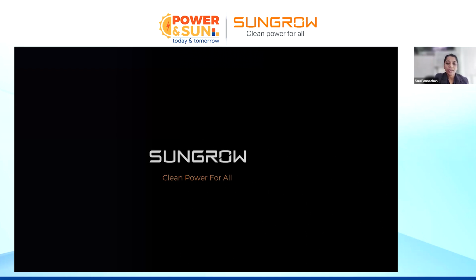Okay. Thank you. We have next question from Mr. Basam. The signal of the load shedding is depending in the current or any other variable? So the signal of the load shedding, from the inverter perspective, because load shedding is when the grid actually goes off in a scheduled manner, right? So the inverter or the solar C&I BESS system will know that there is a load shedding, because we will lose the signal on the grid side. There's no longer voltage signal or frequency signal, so we will lose that part. So once that is gone, the inverter will know, all right, we lost the signal on the grid port. Now this is an off-grid situation, and it will do the seamless switching within 10 milliseconds to convert to off-grid and rely on the battery.